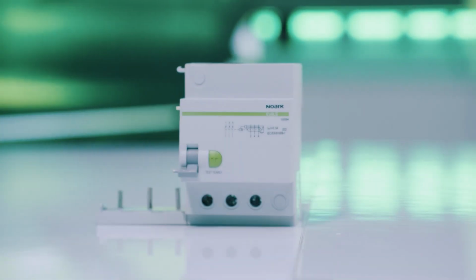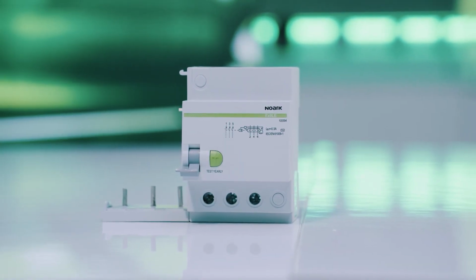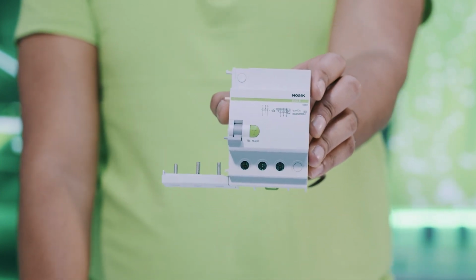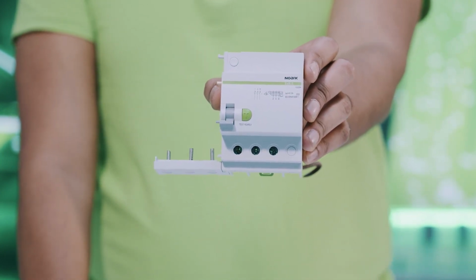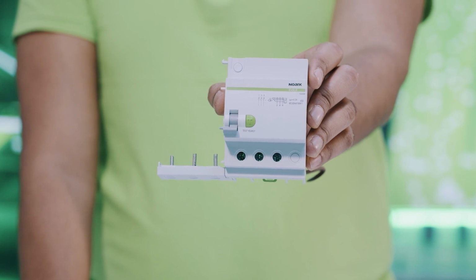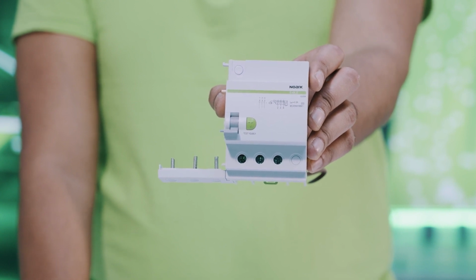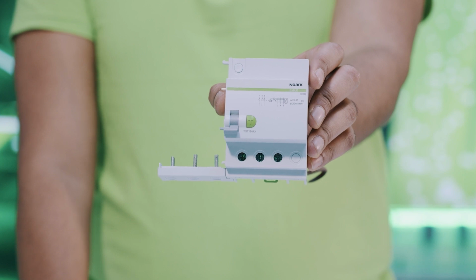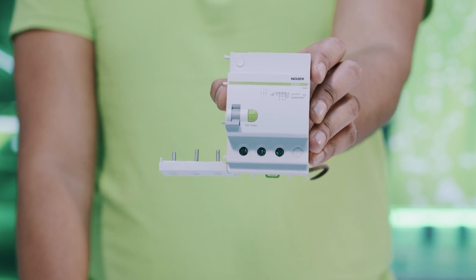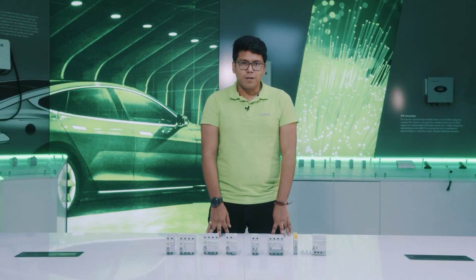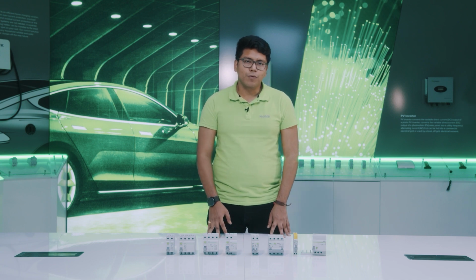The last RCD option in our portfolio is the residual current add-on blocks, EX9LE. They can be combined with our EX9B miniature circuit breakers to provide residual current protection. They are provided from 2 poles up to 4 poles with 63 amps as nominal current with AC type of RCD. Residual current sensitivities are from 10 milliamps up to 300 milliamps.